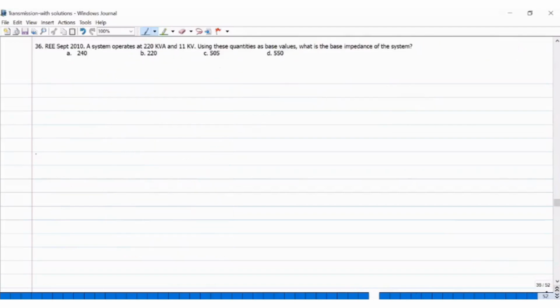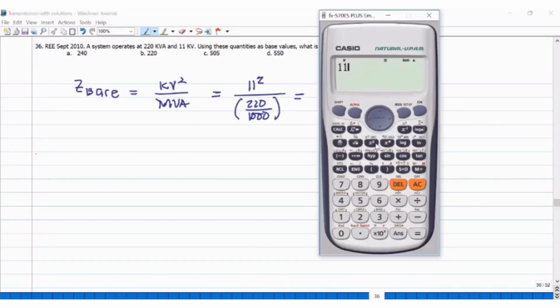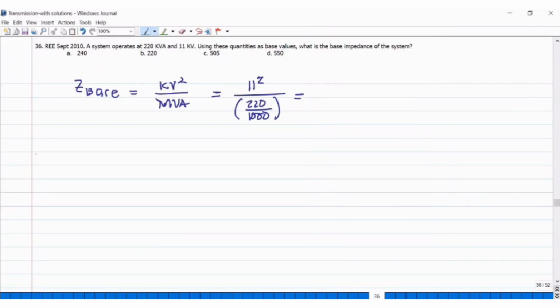Okay, number 36. System operates at 220 kVA and 11 kilovolts using these quantities as base values. What is the base impedance? The base is kilovolt squared divided by MVA. So 11 squared divided by yung MVA, 220 kVA yon. 220 divided by 1,000. So 11 squared divided by 220 times 1,000. So 550 ohms. So 550 ohms, letter D.